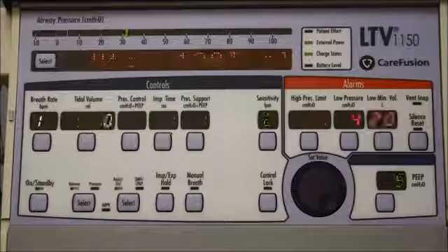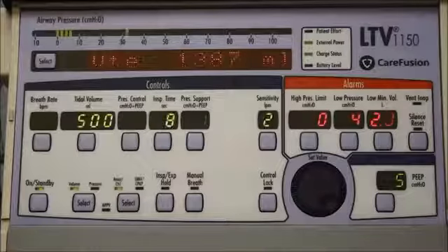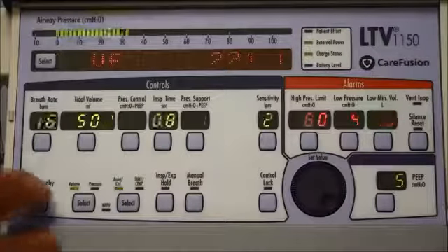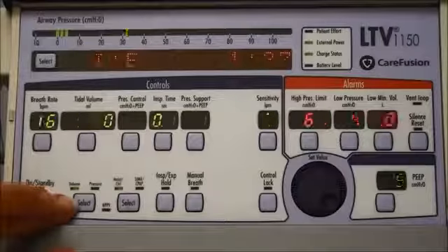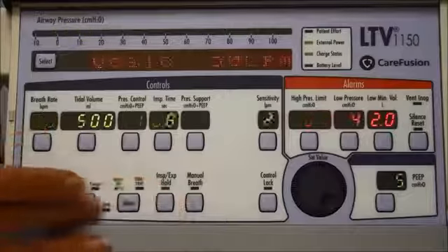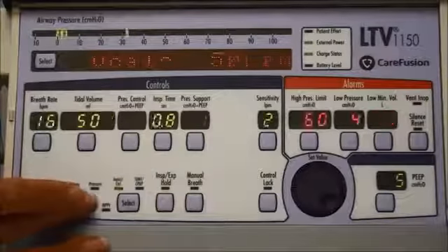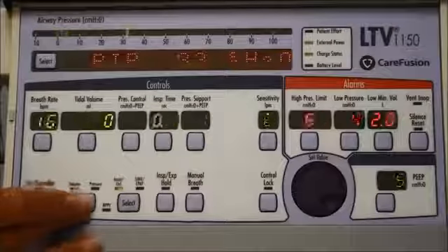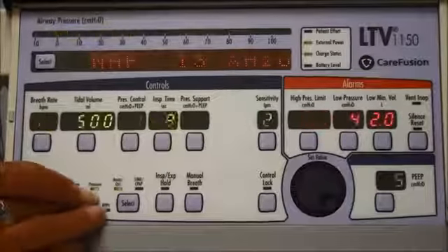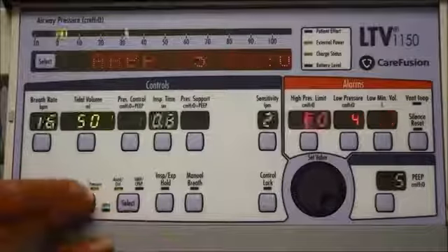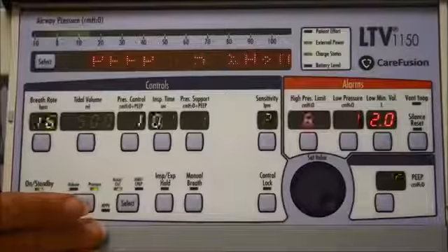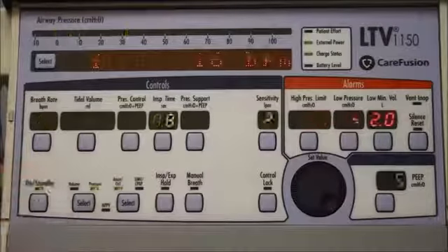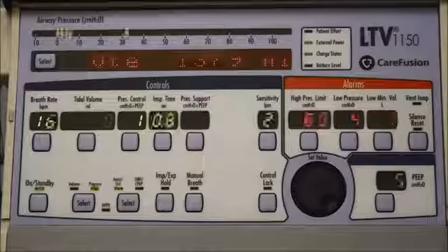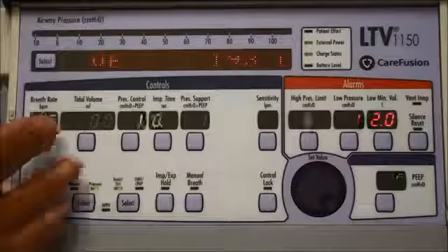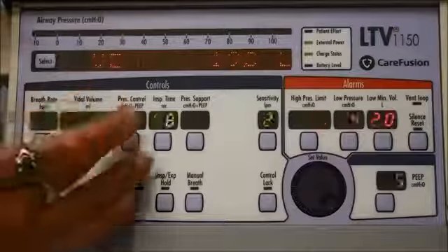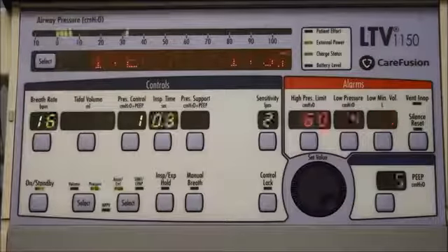Now I'm going to show you what happens if I change to a different mode. Down here on the bottom where the mode selections are, there's a select button, and if I push that button right now, you'll see some things happen. So I'm going to push it. It's going to be flashing the pressure mode. I'll push it again, and now it's going to change so that it's in a pressure and assist control mode. You'll notice that the tidal volume blanked out, and now I have one of the pressure settings.